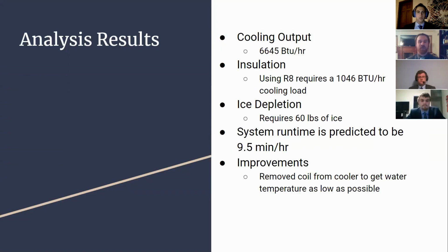Some of the results from our analysis: our cooling output would be 6,645 BTUs per hour. The insulation we would be using is R8, and we would be receiving 1,046 BTU per hour from the outside, and that includes 2 people inside the tent. For ice depletion, we would require around 60 pounds of ice per night with 2 people inside the tent. The system would run for 9.5 minutes total per hour, so after all the cycling is done in an hour, it'd be 9.5 minutes.